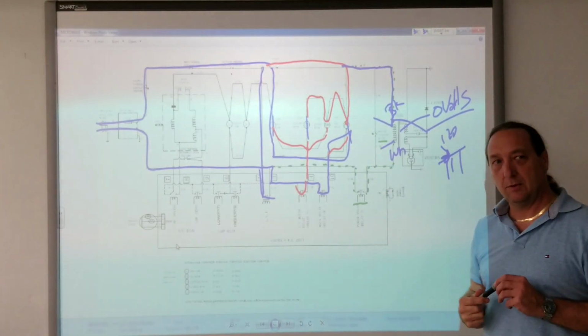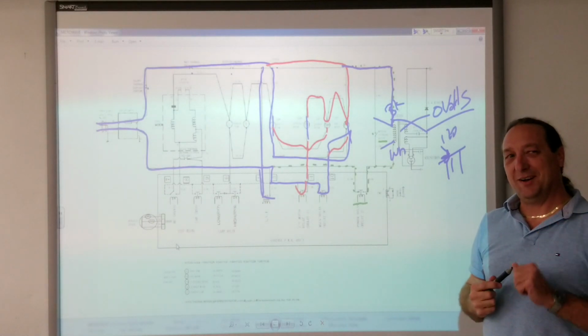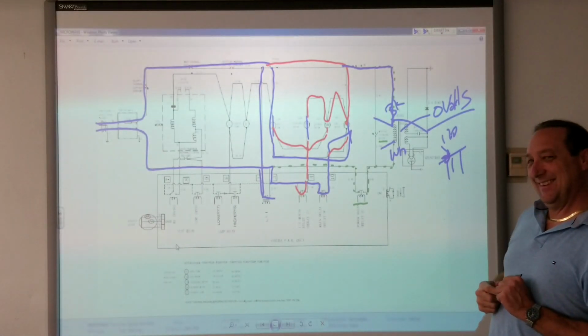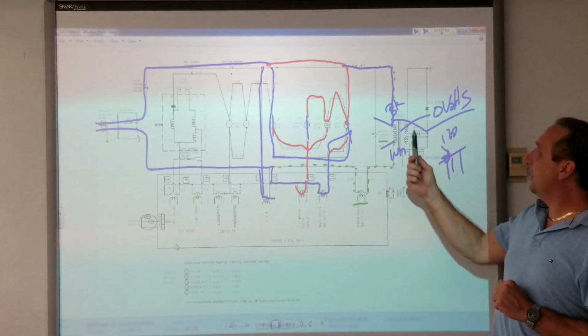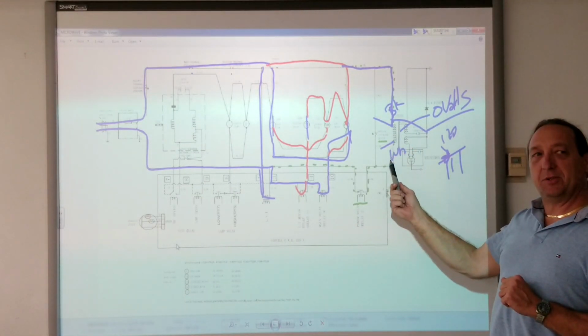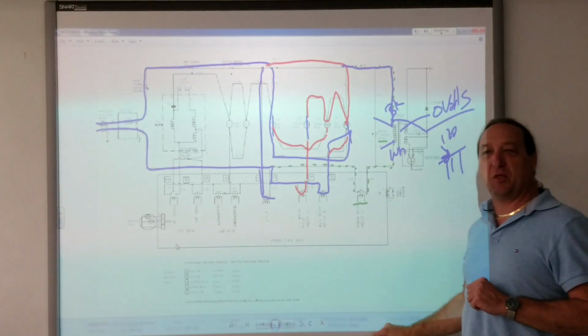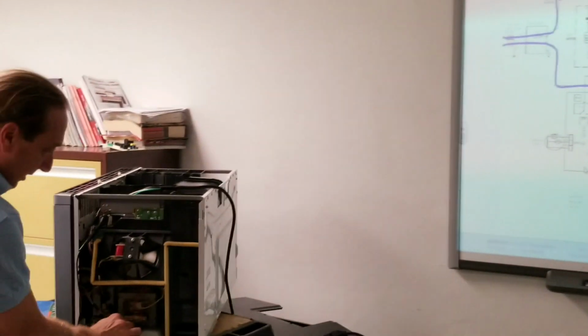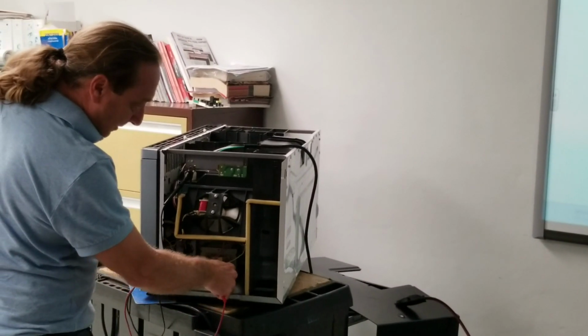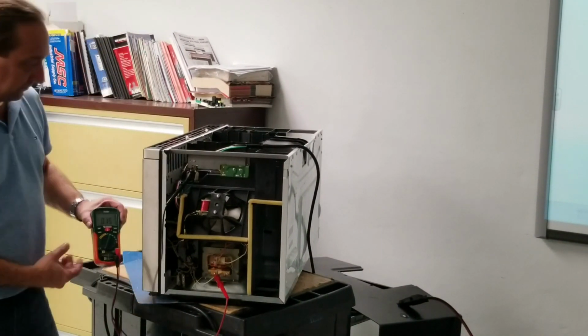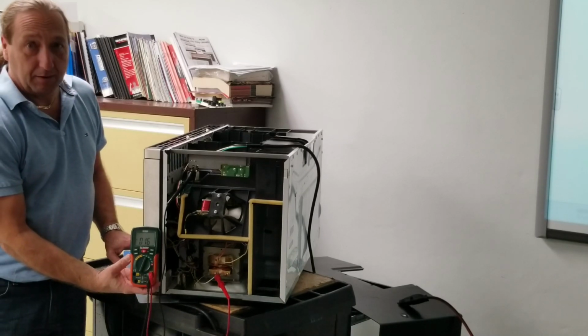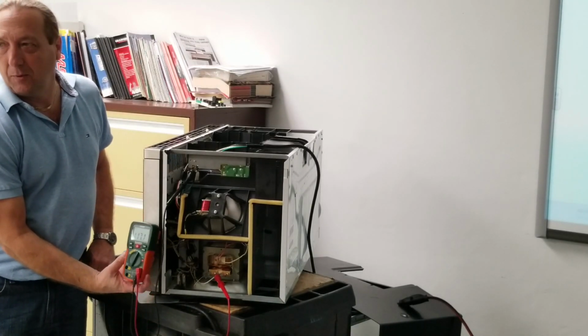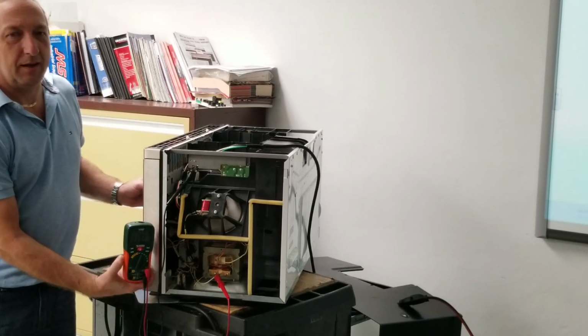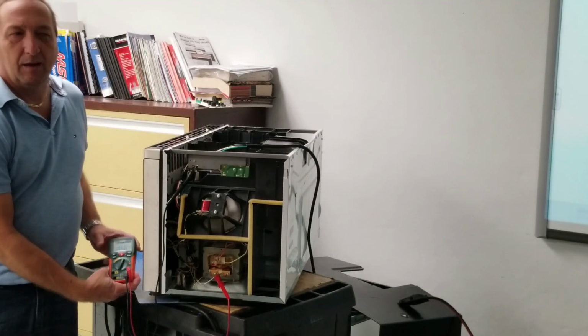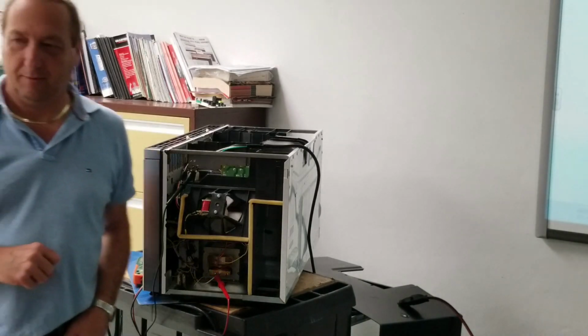Okay, can you do the same thing with the white wire too? Watch. I'm going to take the meter lead that's on black and put it on the white. Let's see, what do you think is going to happen? So I'm going to put this meter lead here, and the other meter lead here, and I'm going to press start. What do I got? 120. So the transformer is open. The transformer is not open. It's not good.